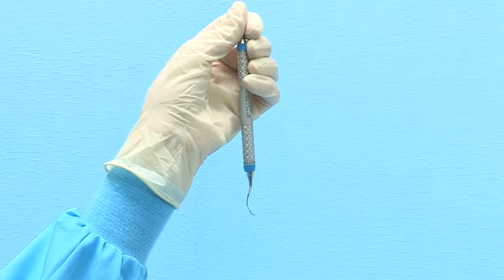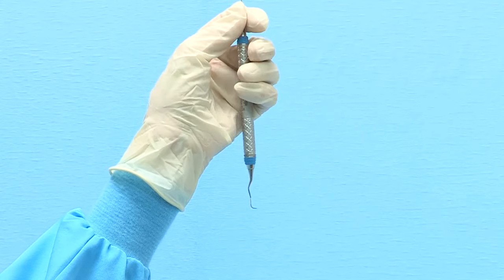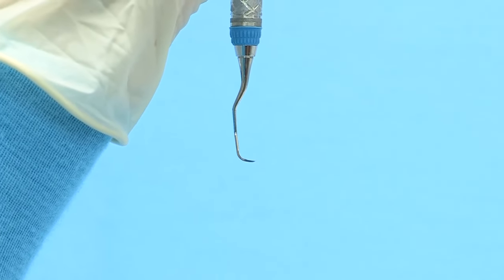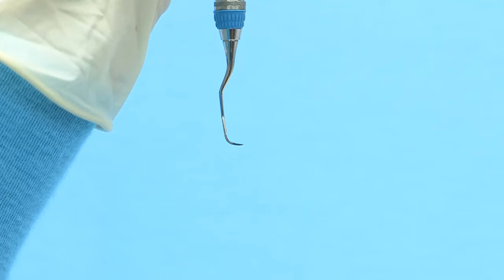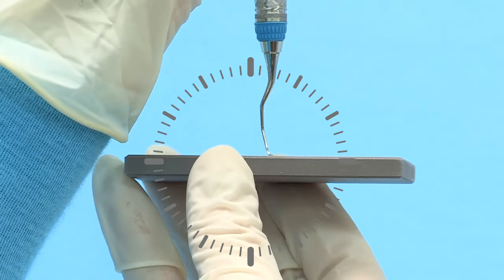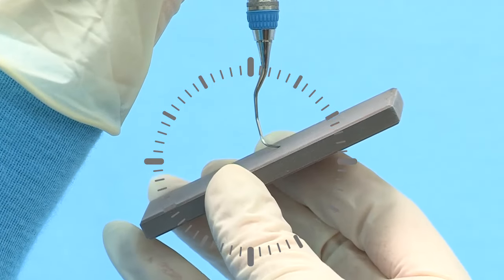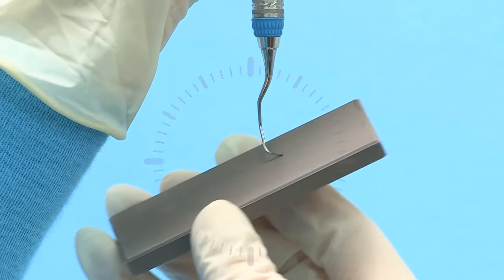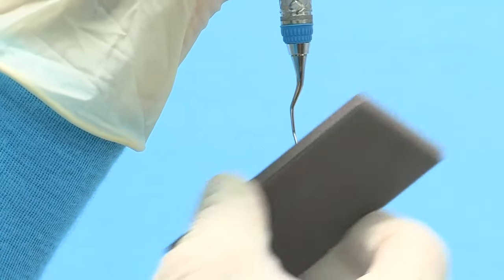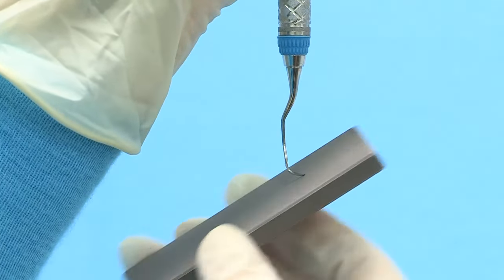When rounding the toe of the even-numbered Gracey curette, rotate the instrument so that the toe is pointed at three o'clock. The face of the instrument should be parallel to the table surface. Position the stone underneath the blade at three o'clock and tilt the stone upward to the two o'clock position. Move the stone in a consistent motion overlapping the strokes and rotating around the toe to maintain the rounded shape.